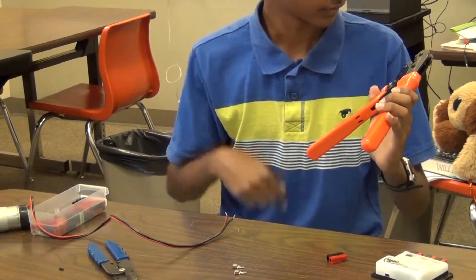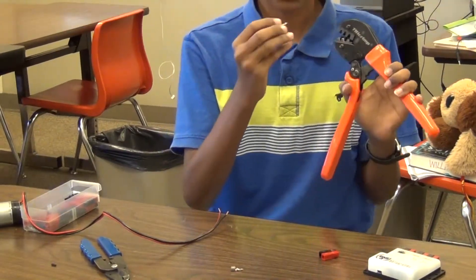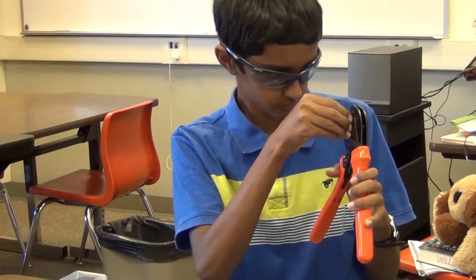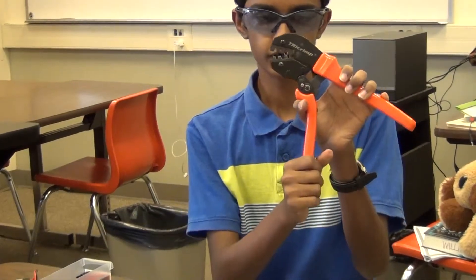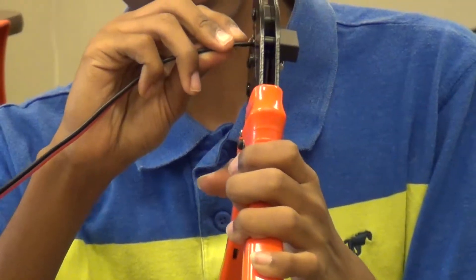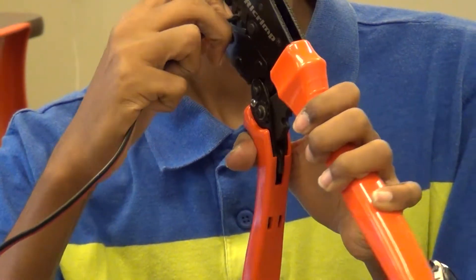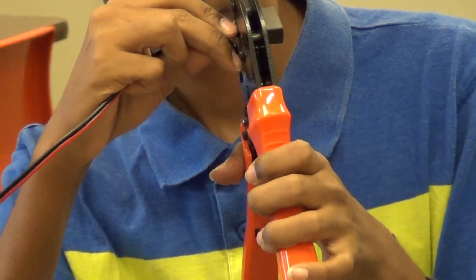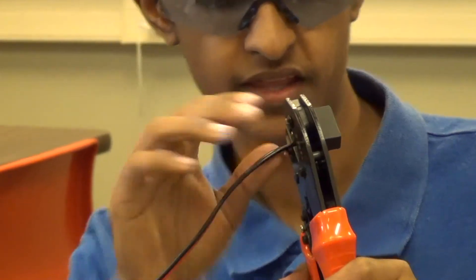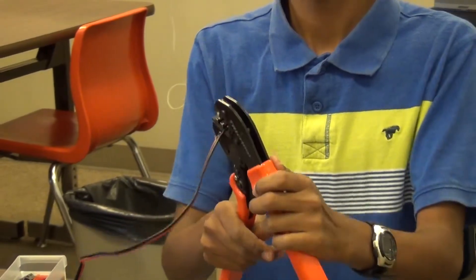This is a 45 amp connector. Put the pin into the 45 hole with the U-shaped part facing up. Then put the wire inside the hole and crimp together. When it stops clicking, it's done.